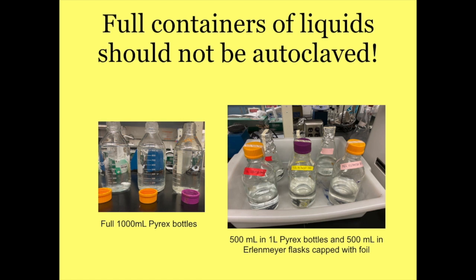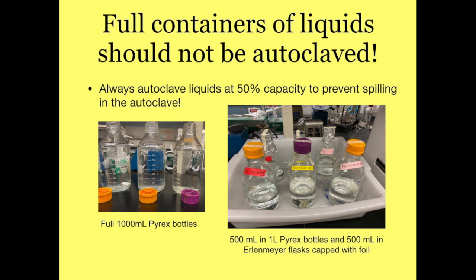Again, full containers of liquids should not be autoclaved. Always autoclave liquids at 50% capacity to prevent spilling in the autoclave. On the left, we have 3 full 1,000 milliliter Pyrex bottles containing MD solution. We do not autoclave like this.